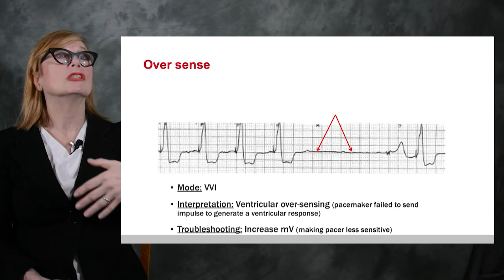Okay, I want to make sure we appreciate this was a very quick overview of pacemakers. This does not supplant your need to really understand pacemaker therapy. In your little book that I've put up in the folder of miscellaneous, I've asked you to go to the Medtronic Academy and take all of the pacemaker classes there, take the test, give me the certificate. But always know what mode your pacemaker is set at. You look at the pacemaker for that. Use the milliamps necessary to capture, and don't use any more milliamperage than you need to capture the heart.